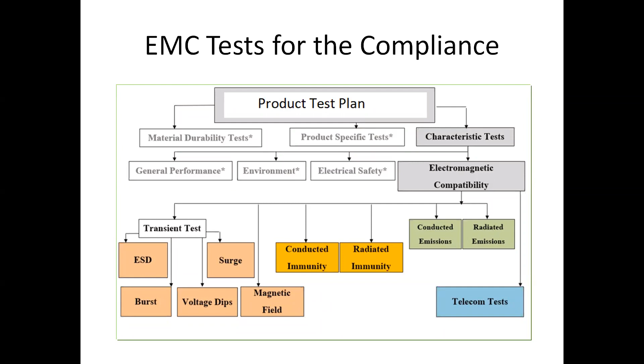So if you take any product, a test plan has to be followed, and the test plan of the product can be the characteristic test, product test, and the material durability test. So our electromagnetic interference and electromagnetic compatibility test falls under the category of characteristic test, which is the electromagnetic compatibility level, and there are basic 5 tests to be conducted. As we saw in the previous slides, we need to concentrate on the conducted immunity, radiated immunity, conducted emissions, and radiated emissions. After that, we have to test for transient tests like ESD, burst and surge, voltage dip, and magnetic field. So these tests have to be done in the EMI laboratories before releasing the final product. This can be an IoT product or any other system or package.